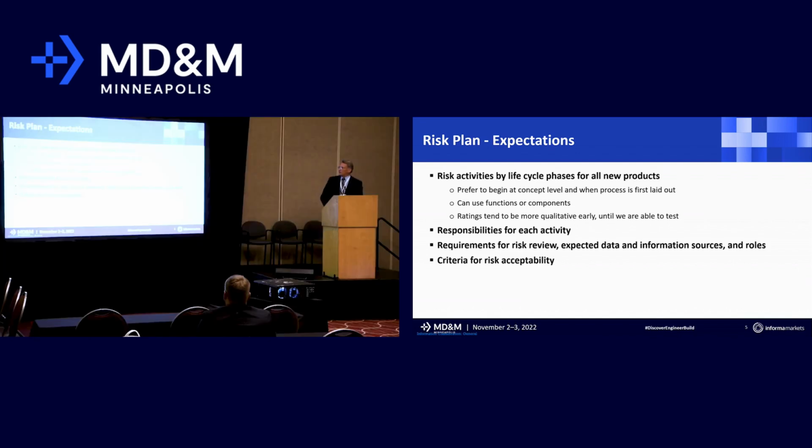And the criteria for risk acceptability comes back into that quantitative, qualitative concern. But you need to have that in there. And I'm finding that organizations, for whatever reason, are using the standard change as an opportunity to change their rating system, which means their acceptability levels change, which means there's no traceability history going forward. My own personal recommendation is don't change those things. Try and keep that consistent. But for some reason, I'm seeing a lot of organizations make changes in both areas.